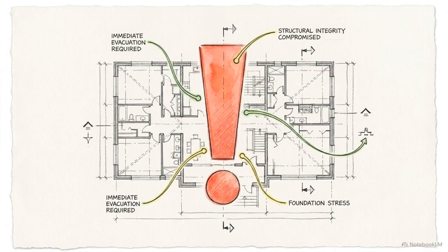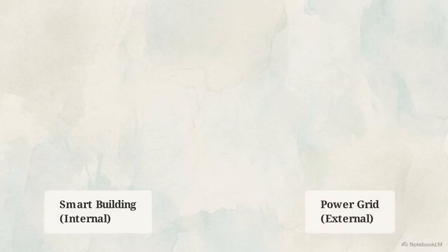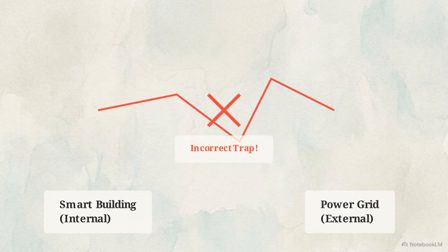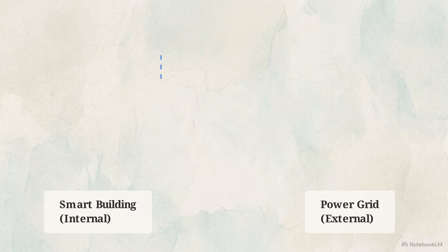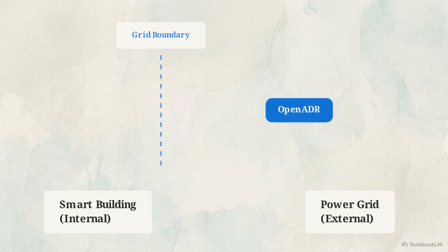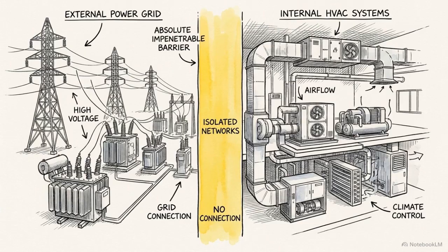This brings us to a massive conceptual trap in systems design, confusing the internal building communication with external power grid communication. You will encounter protocols like OpenADR. It is strictly used by the external power grid to send demand response signals to a building, asking it to reduce power. The boundary is absolute. Grid-side protocols talk to the building as a whole. Field-side protocols talk to the physical hardware. You never mix the two.